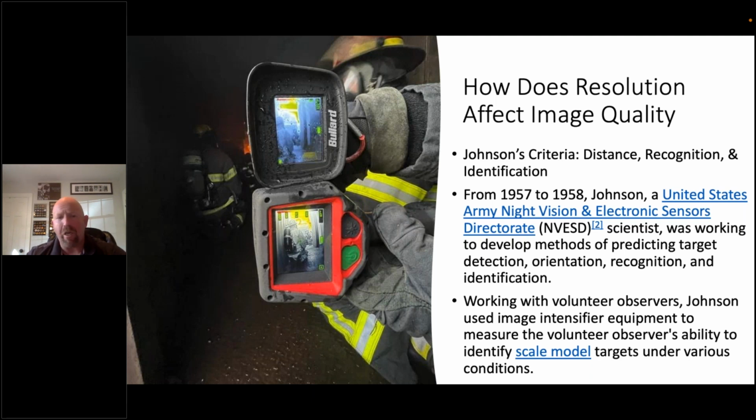I know I should wipe the lens, but hey, just a gee whiz question. Which one? I mean, they all say they got 320 by 240. Why are they all the same? Well, 320 by 240 is the resolution of the detector. A lot of them say 76,800 pixels. But when you start adding software and all the things they do with them, each camera produces a picture differently, and the manufacturer does their own proprietary program. Here's two cameras that have the exact same pixel count producing different image quality.